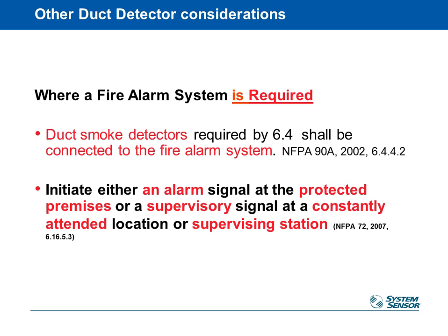And then I have to initiate either an alarm signal in the occupied area, in the protected area, or a supervisory signal back at a monitoring station that's occupied 24/7, like a guard station or something like that. The most common way to do it would be in the occupied area.